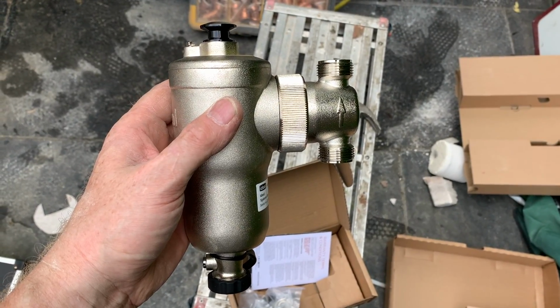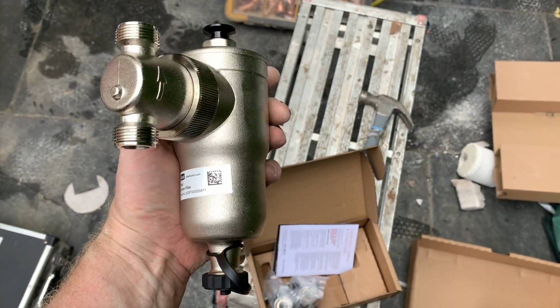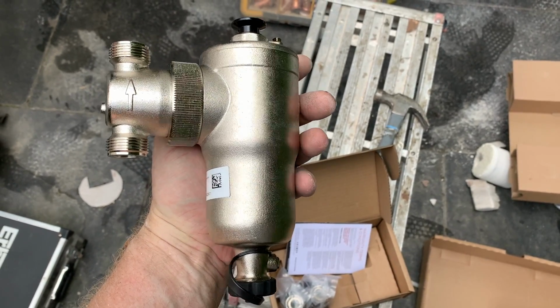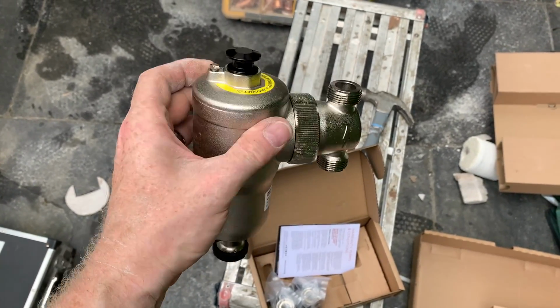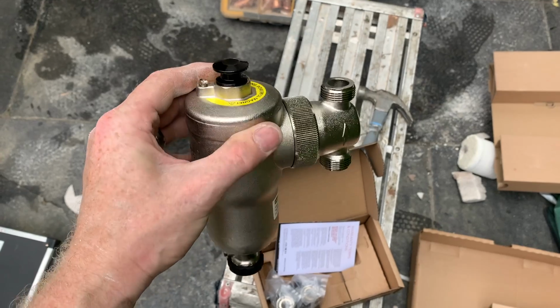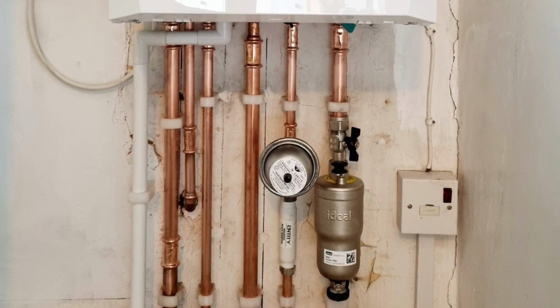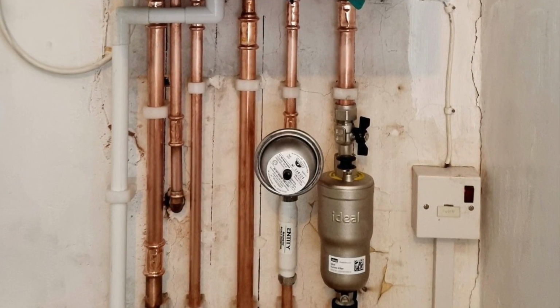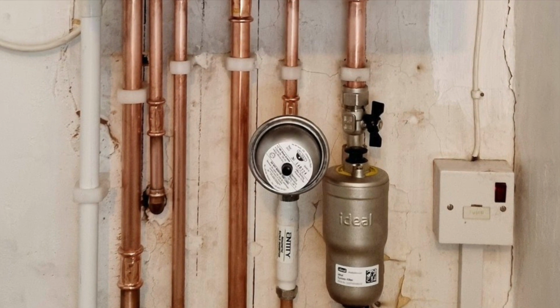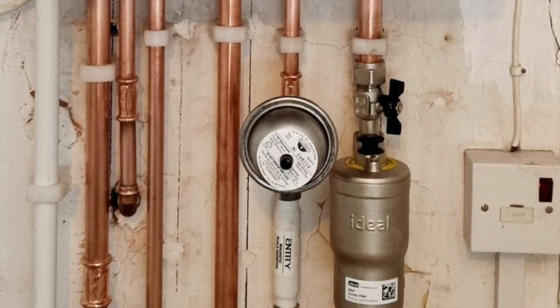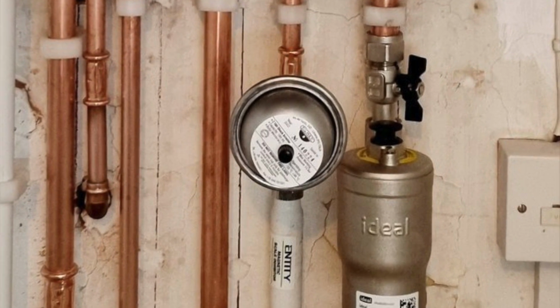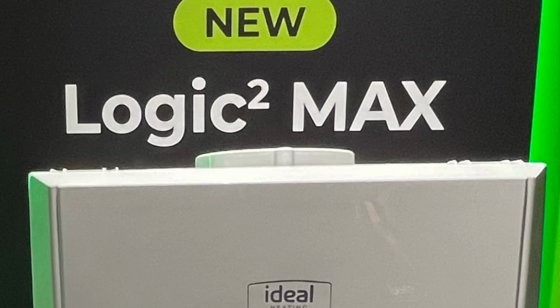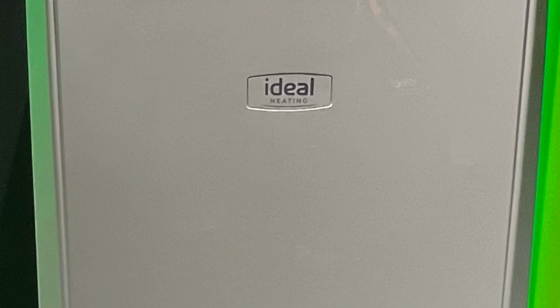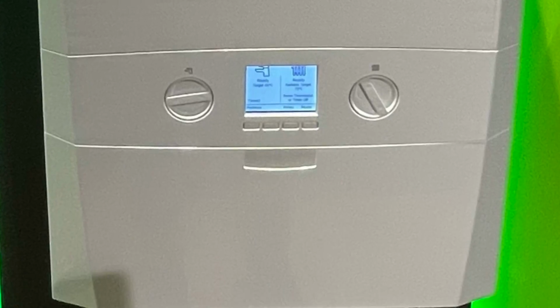Now the max range of boilers comes with this magnetic filter, which could extend the warranty of your boiler. But it doesn't come with this mini expansion vessel, which you may have to fit if you have a water meter or a non-return valve installed on the cold water supply. So that's the changes Ideal have made to their Logic range of boilers. Or is it? Hold on a minute.